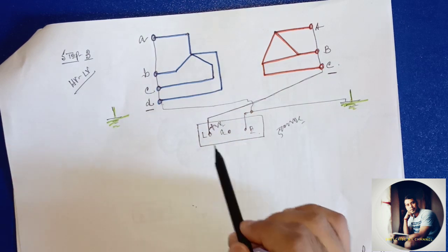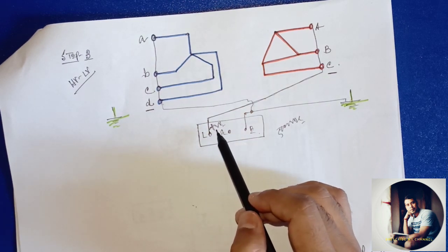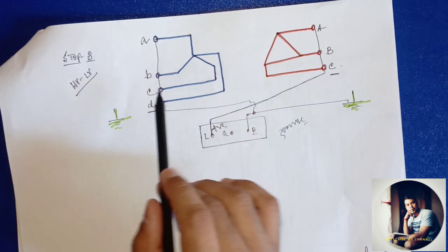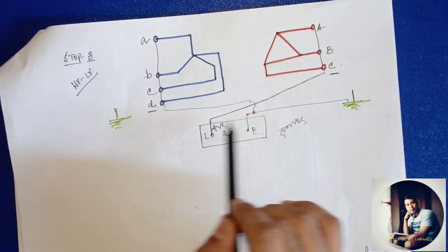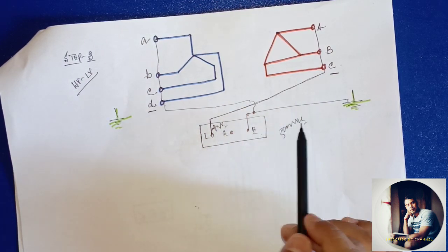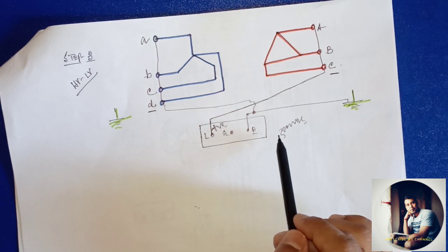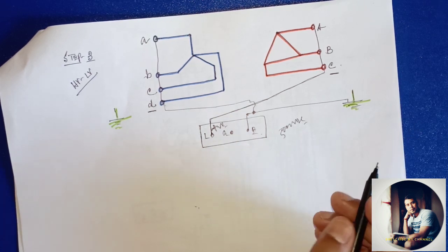So you have to be very sure that the positive terminal gets connected with the high voltage side, and your secondary side, after shorting it all, gets connected to the earth, that is also connected with the megger earth. In that case you also get the high voltage to low voltage IR value.